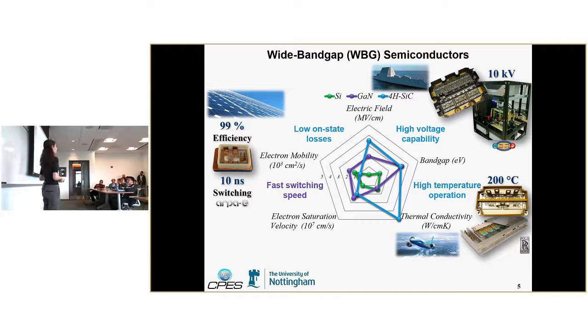Anything above 6.5 kV for a silicon IGBT becomes too lossy; it's not worth doing. So we actually got our hands on the first generation 10 kV, 120 amp power modules, and with those we built power electronics building blocks, or PEBBs, a concept developed by the Office of Naval Research some time ago.